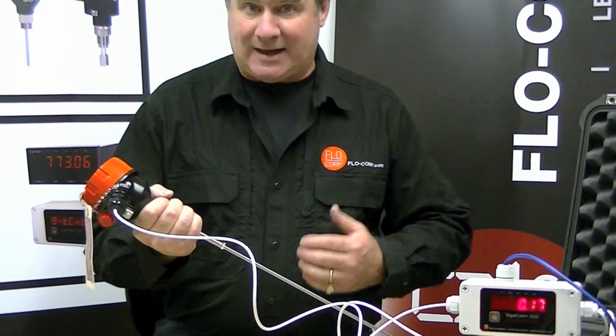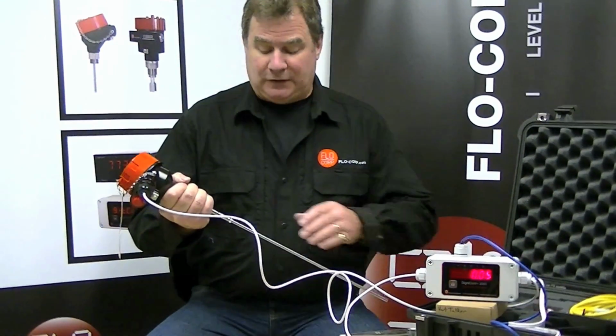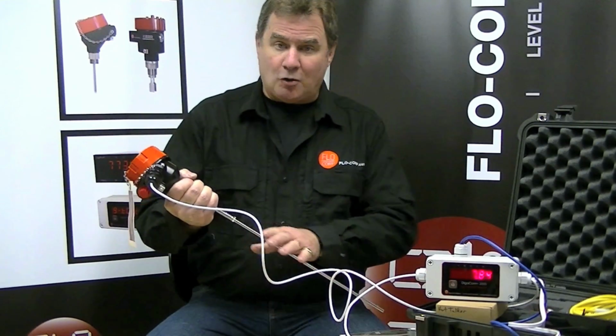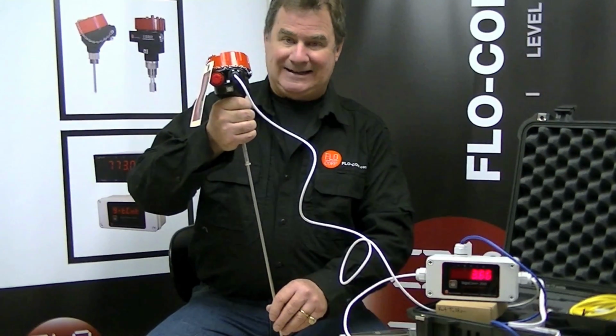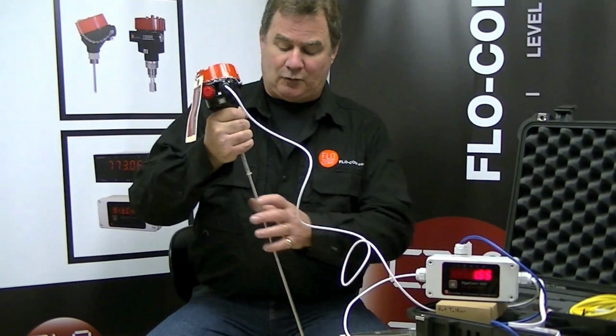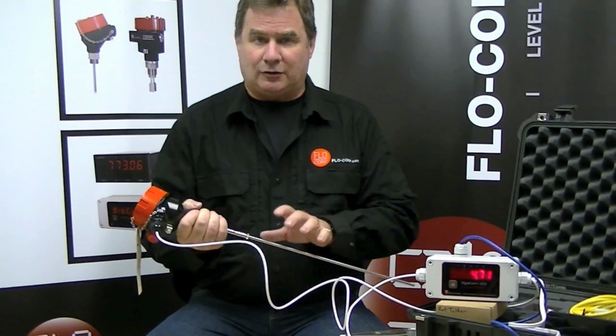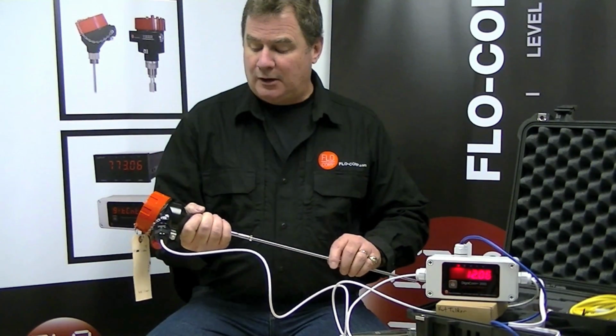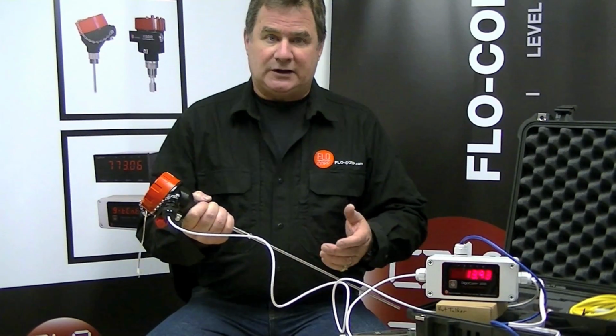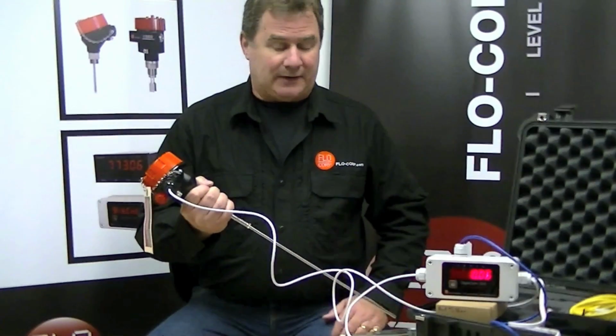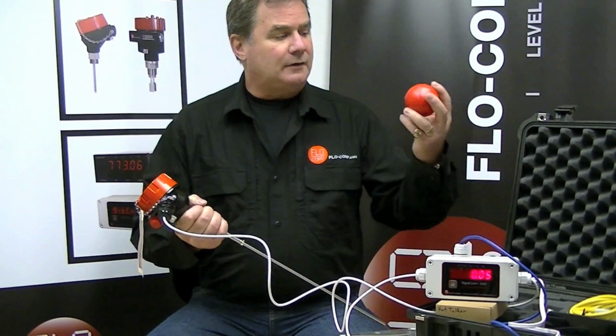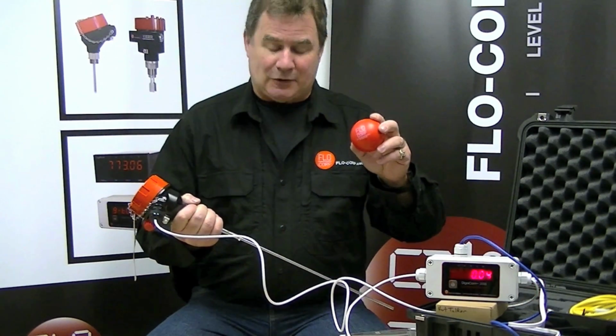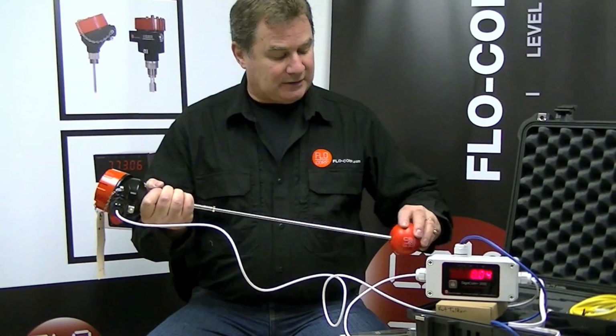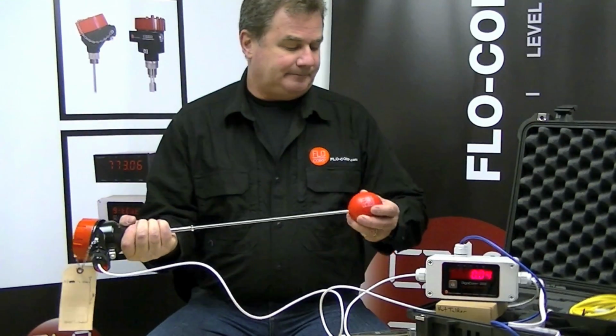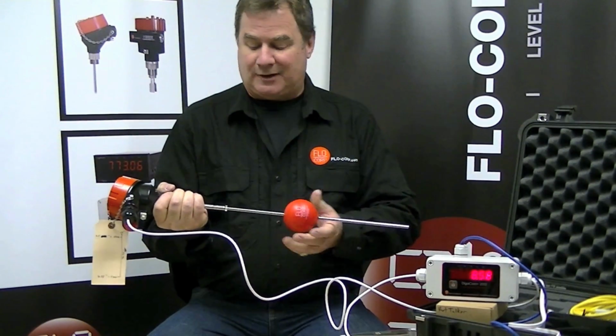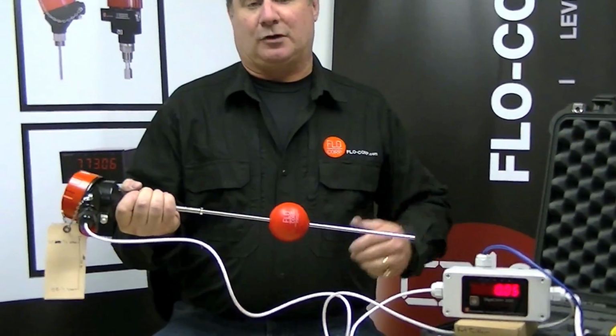One of the first questions that may come up is, well, you're telling me that the transmitter probe has to be placed in my tank, and my concern would be that an emulsion or buildup may occur on the probe, and in which case, how's that going to affect the level signal? For this reason, we have the red ball in the demo kit, and you can simply insert the red ball into the probe, and you can place the red ball anywhere along the 18-inch probe length.